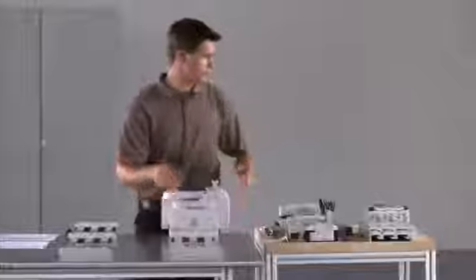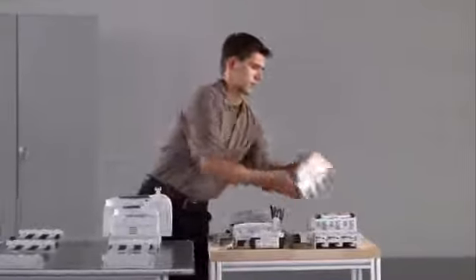The springs guarantee the contact pressure and ensure a lifetime of power transmission, irrespective of operator skill. The contact point cannot be loosened by vibrations. The fact that no drilling is needed to mount the devices means that the system can be constructed extremely quickly and efficiently. The multi-pole components of the 60mm bus bar system technology simultaneously guarantee shock protection for the system.